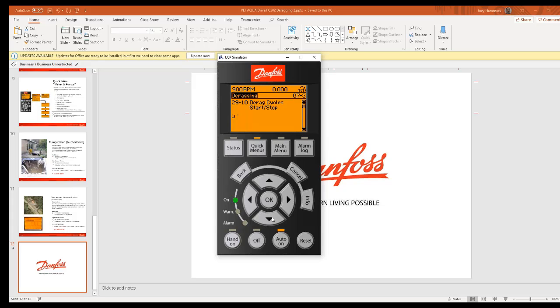So we had 3 cycles here, right at start. For showing it, I'm going to set it really fast so we can see it run. So I'm going to do 3 seconds. I'm going to set the deragging speed at a slower speed than my reference. I have a 900 RPM reference up here, and we're doing it at 600. Do you have an actual motor there? I do. DERAG power factor, I'm not going to worry about that, since this goes into the power. So I'm just going to do the dwell time one.